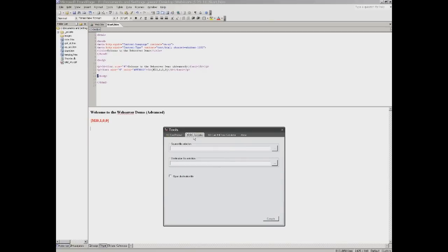It will format the code that you have written, the HTML pages. It will make sure that they are in the proper format to go onto the SD card. Summarizing, that's the basic concept of what it's doing. Specifically, our PLC accesses the SD card in 512-byte chunks. That's just how the operating system on the PLC handles anything with the SD card, whether it's using data tables or writing trends to the SD card.